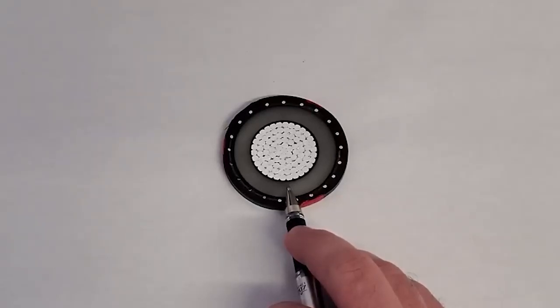So the XLPE is more efficient. It has about a 25% higher breakdown strength and 70% higher impulse strength. Impulse strength is high voltage, high current for a short pulse. This XLPE is good from -40 to 105 Celsius with an emergency rating of 140 C. I don't remember what the duration is for emergency rating. I want to say 2 hours.